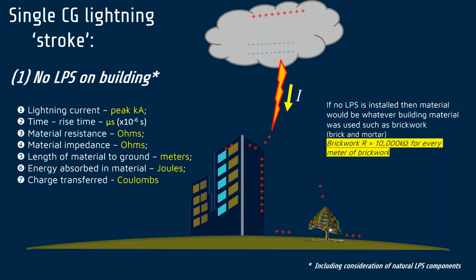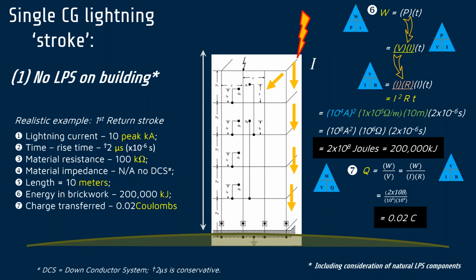So when we start putting real numbers in, I mentioned the peak value of 10 kilo amps. If we're talking about only a single lightning stroke, typically a first return stroke would have a rise time of about 5 microseconds, so I've conservatively made it less, giving a smaller number. With 2 microseconds, the material resistance is 100 kilo ohms, 10 to the power of 5.